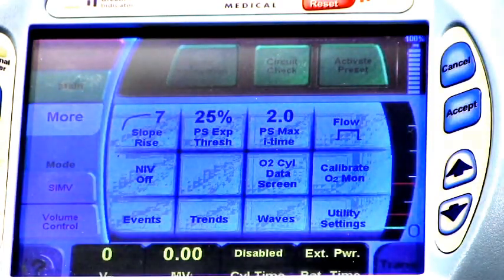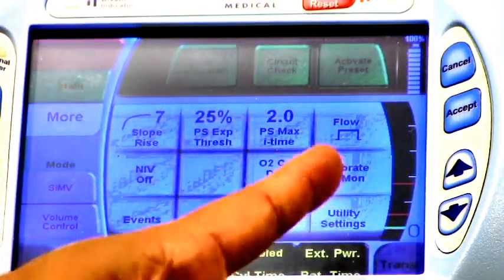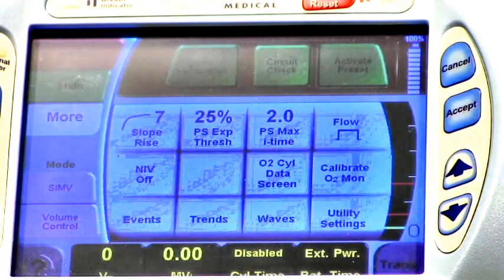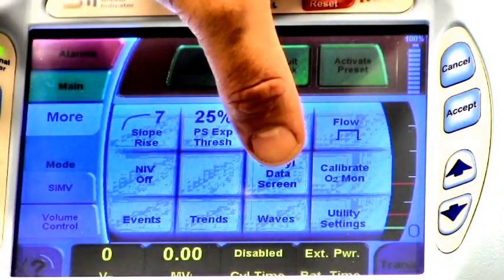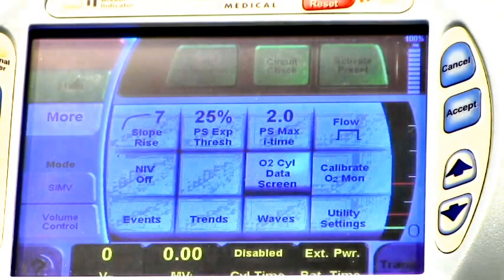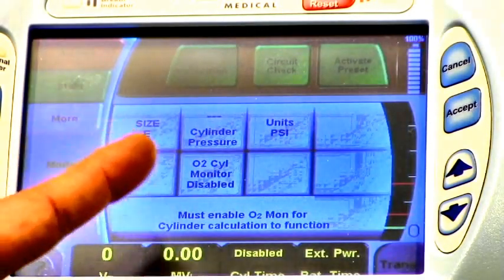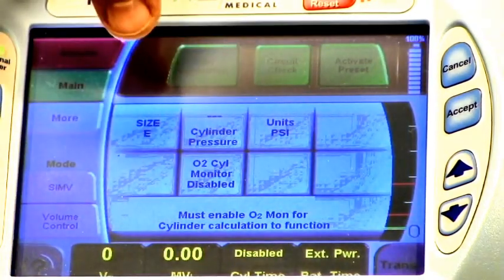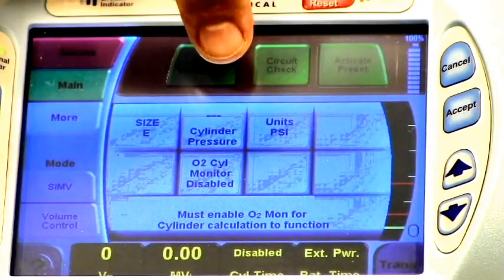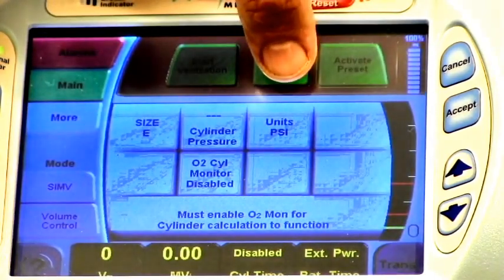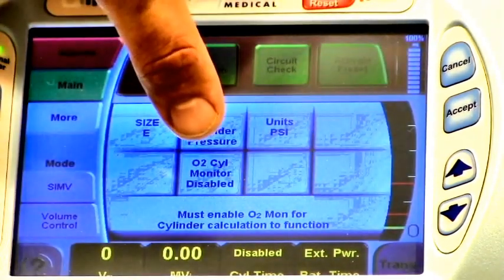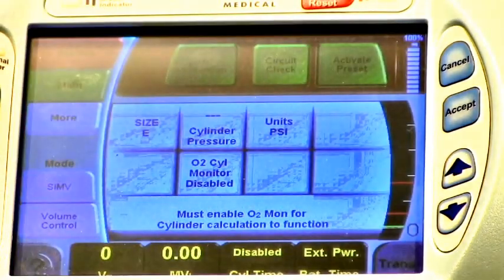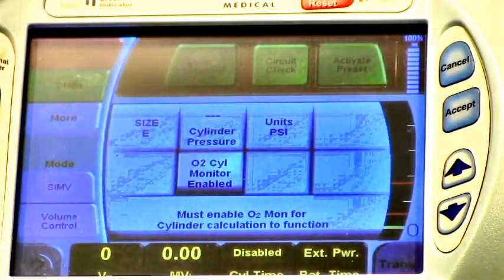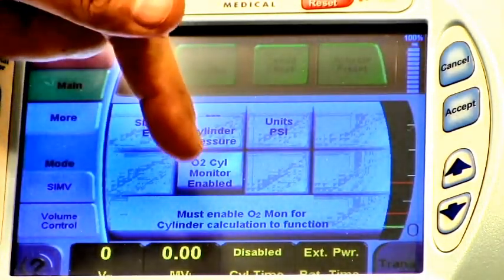On the more screen you have an O2 cylinder data and you have a calibrate O2 monitor. So what we're going to do is first touch the O2 cylinder data screen. It's going to show us the different sizes of tank. Right now it's set up for a size E. Cylinder pressure has not been entered. The units are in PSI, which we want to maintain, and our O2 cylinder monitor has been disabled. So the first thing we want to do is enable the O2 cylinder data. That's going to allow us to do it, so now it says enabled.